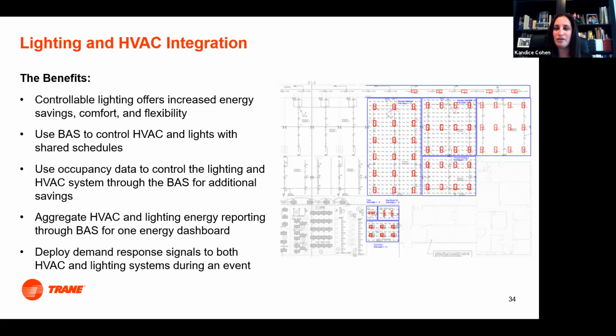One thing we can do that's really slick with integration is, over the course of two and a half minutes, dim lights 50% without the human eye detecting a difference, because of how our pupils respond to light. For a short period—a few hours—we can reduce light levels in a space without any negative impact on occupants. Your company can get revenue from participating in the demand response event, and it can have an annual impact on your energy bill.